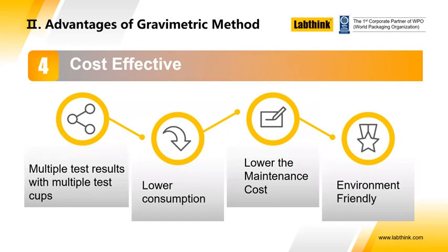So there are some advantages to working with the gravimetric methods. As I mentioned, you can refer to it as an arbitration or definitive method. There's no limit to the number of cups or dishes that you can put into an oven. You're only limited by the size of the oven. In the case of our automated equipment, we have instruments which can measure WVTR in 3 test dishes or cups, up to 6, and further up to 12 samples.